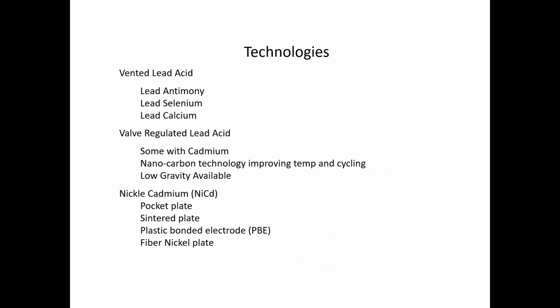So vented, flooded batteries, even there you have different technologies, different float voltages, different maintenance routines: antimony, selenium, calcium, or some of those. The valve regulated, for the most part, they're pretty standard. They do have some batteries with cadmium in them. That's the older Absolyte series batteries from GNB. So consideration needs to be given when recycling. Not a lot of smelters will take batteries with cadmium in them.